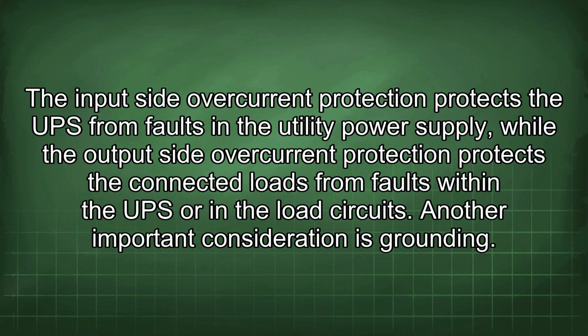The input side overcurrent protection protects the UPS from faults in the utility power supply, while the output side overcurrent protection protects the connected loads from faults within the UPS or in the load circuits.